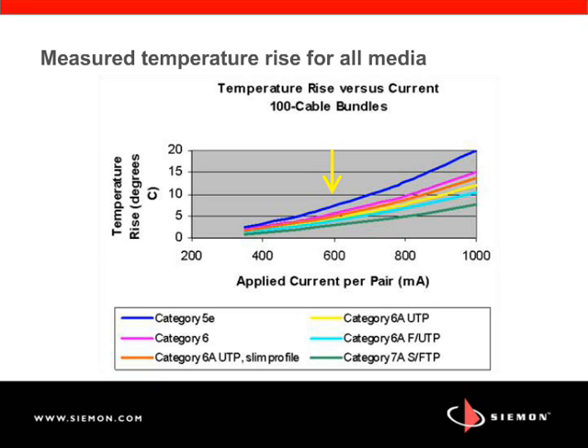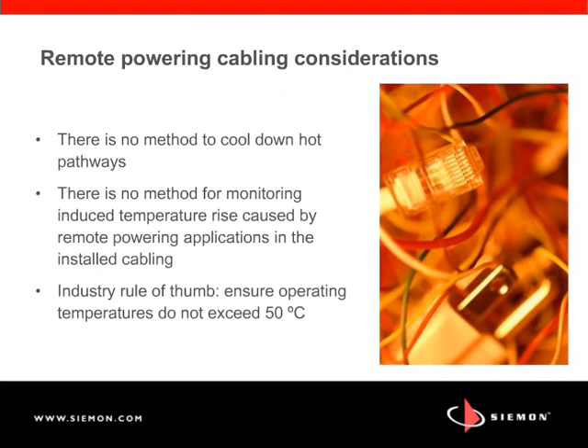The temperature rise within a category 7A bundle associated with the PoE Plus application is 2.8 degrees C. So let's talk a little bit about what we've learned here. We know that remote powering applications cause some heat to build up in the cable. We also know that there's no method to cool down hot pathways, and there's no way to monitor temperature rise.